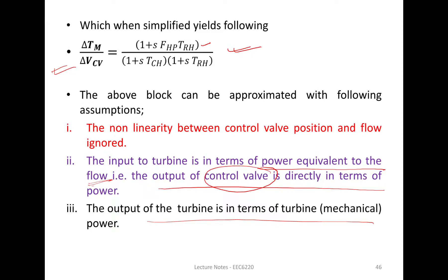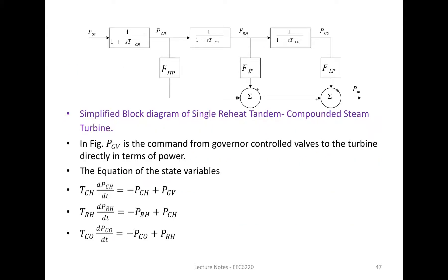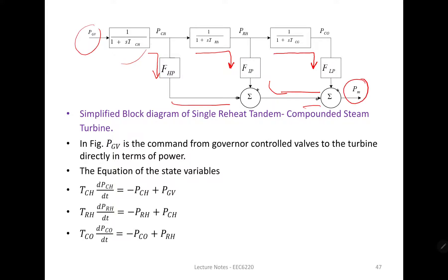To summarize the simplified block diagram: steam enters, the high pressure turbine generates its fraction of power, then after a time delay the intermediate pressure turbine generates its fraction, then through the crossover piping the low pressure turbine generates its fraction. All three power outputs are summed to give the total mechanical power output. That is all about the steam turbine model; in the next lecture we will discuss about the governor.